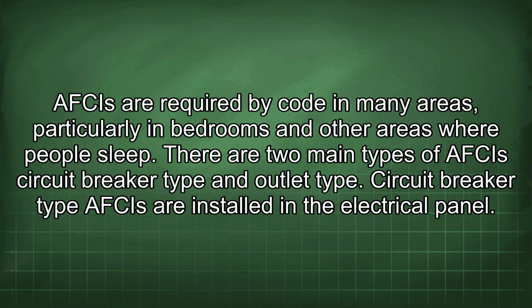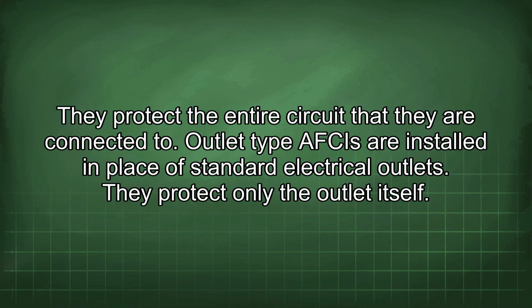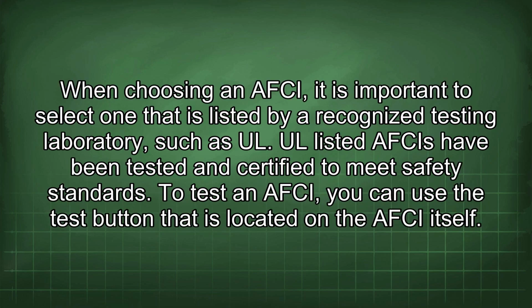Circuit breaker type AFCIs are installed in the electrical panel. They protect the entire circuit that they are connected to. Outlet type AFCIs are installed in place of standard electrical outlets. They protect only the outlet itself. When choosing an AFCI, it is important to select one that is listed by a recognized testing laboratory, such as UL. UL-listed AFCIs have been tested and certified to meet safety standards.